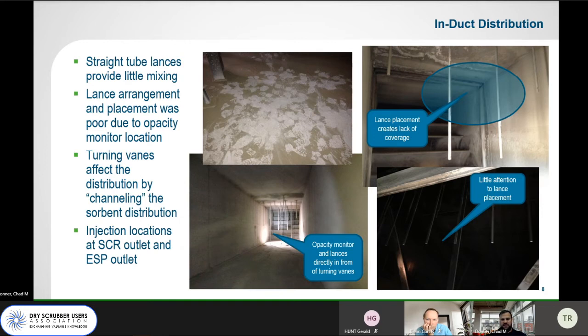And they were chosen, that location. This is the ESP outlet location as an SO3 polishing step. In the lower left picture, there is an opacity monitor that they were still complying on. So they put the lances directly downstream of the opacity monitor, which again put it directly in front of the turning vanes. So not an ideal location for getting good mixing and reaction with hydrated lime. Bottom right is the SCR outlet injection lances. I don't know who thought that would be a good idea, but all of the lance lengths are exactly the same, in the center of the duct, all the way across the duct. Not a good way to get good distribution. And top left, there's a lot of hydrated lime laying on the floor from just lack of mixing and material layout.